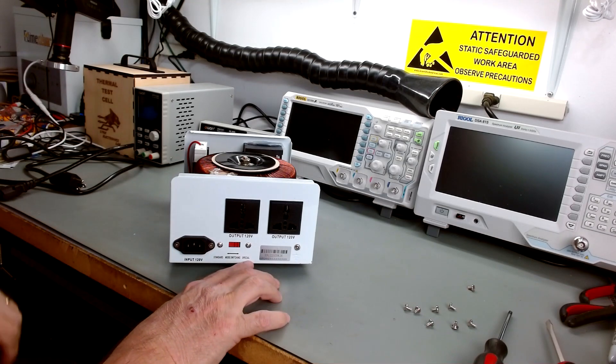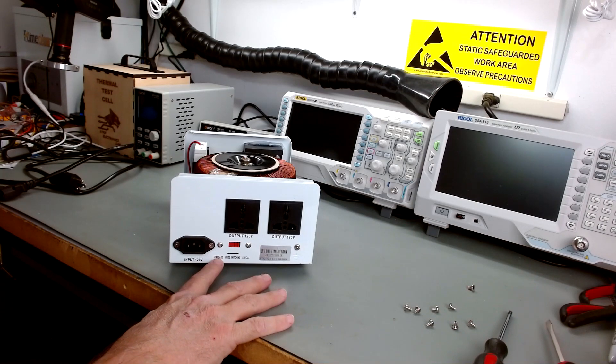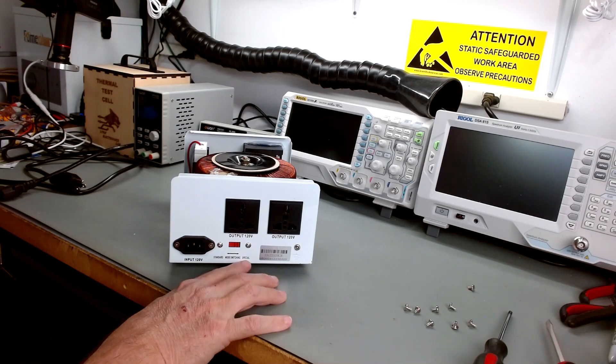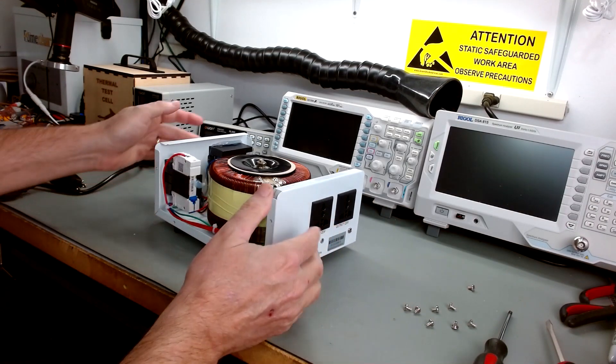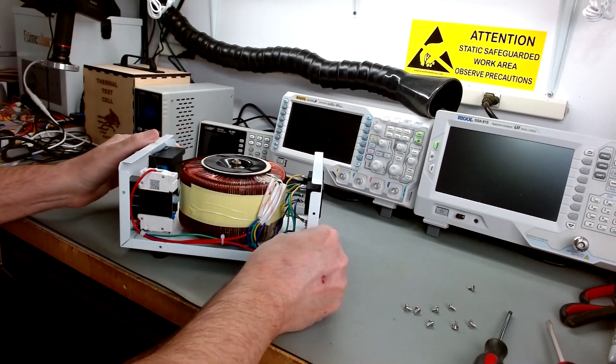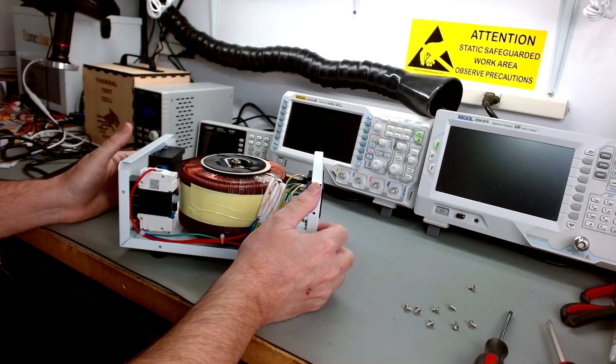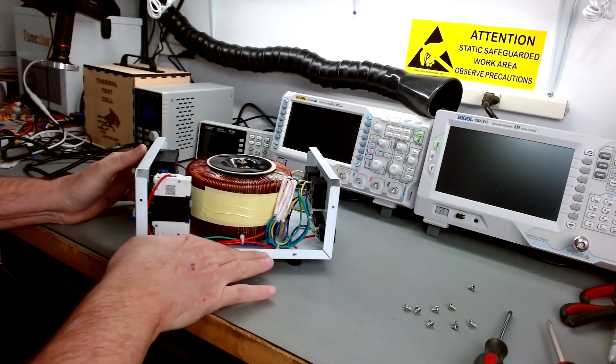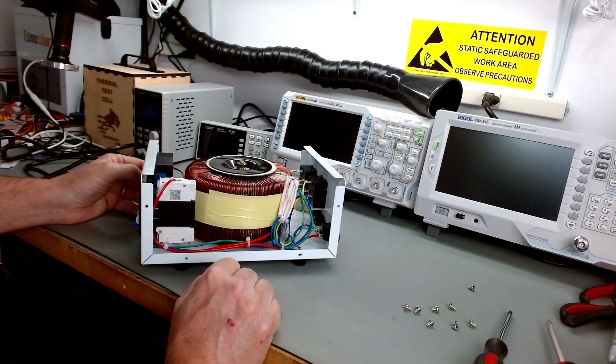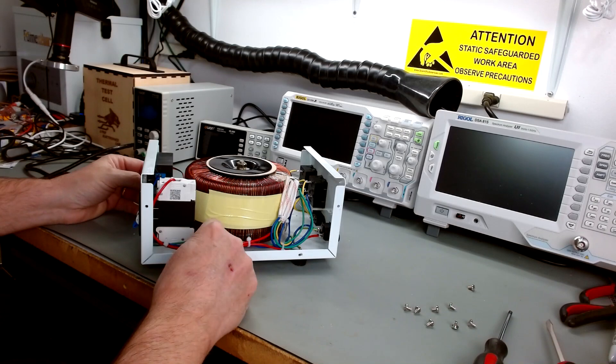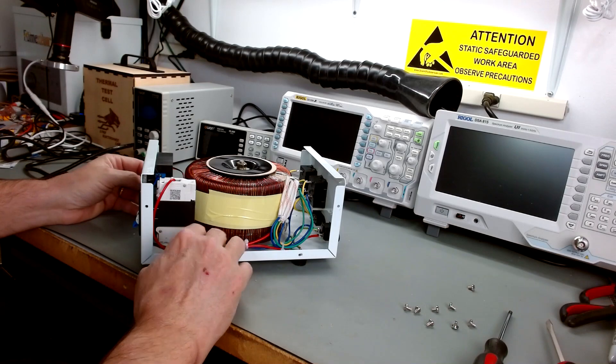This is the switch I was talking about. You have a standard and a special mode. Standard allows the ground to pass through, continues to pass the ground through. The special cuts off the ground so that you have no, nothing from the line side, the supply side passes through to the output. This thing is a one KVA rated. It's not as heavy as my Variac. And you can see the cables are a little smaller gauge, but still looks sufficient for 10 amps.